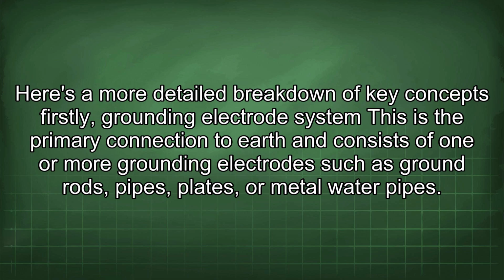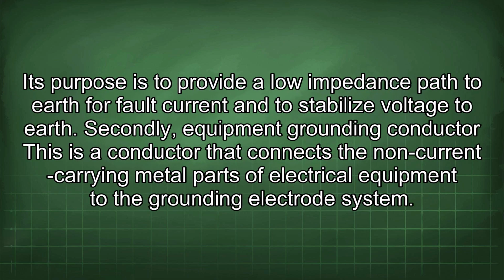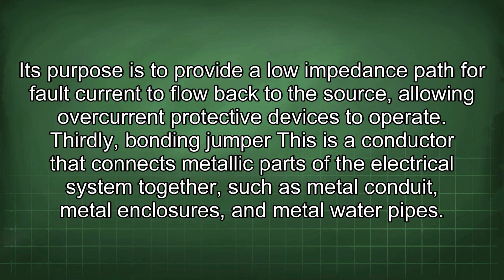Firstly, grounding electrode system. This is the primary connection to earth and consists of one or more grounding electrodes such as ground rods, pipes, plates, or metal water pipes. Its purpose is to provide a low impedance path to earth for fault current and to stabilize voltage to earth. Secondly, equipment grounding conductor. This is a conductor that connects the non-current carrying metal parts of electrical equipment to the grounding electrode system. Its purpose is to provide a low impedance path for fault current to flow back to the source, allowing overcurrent protective devices to operate.